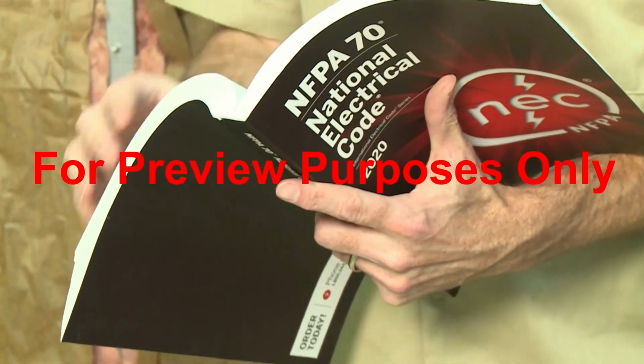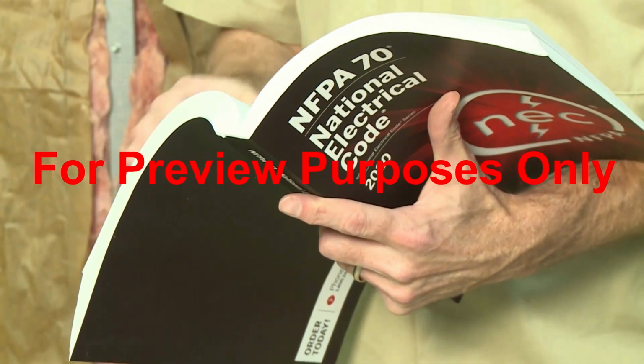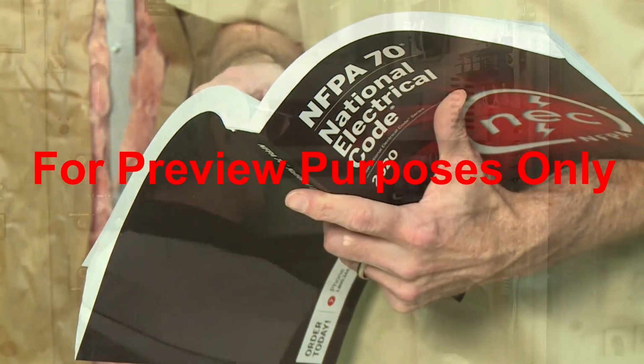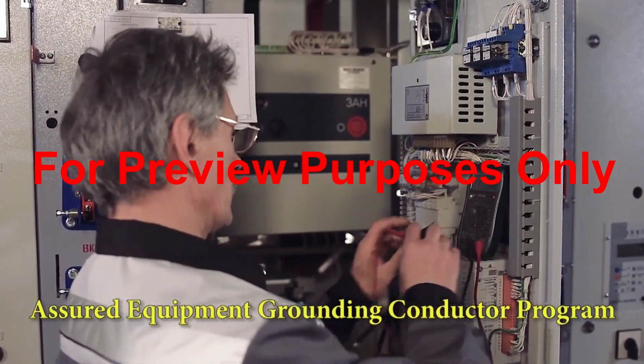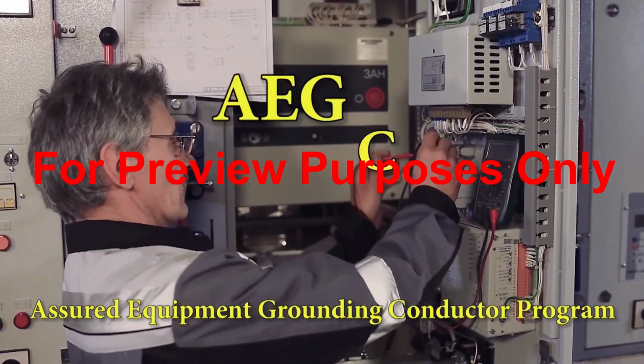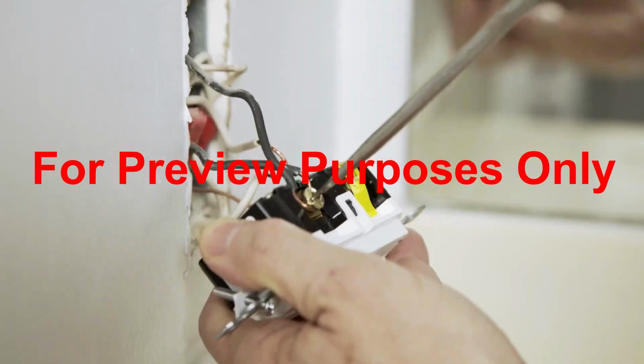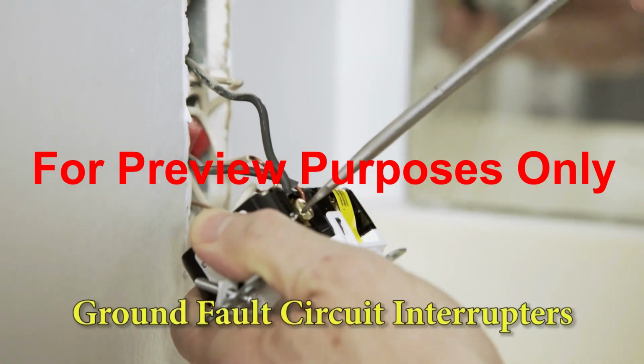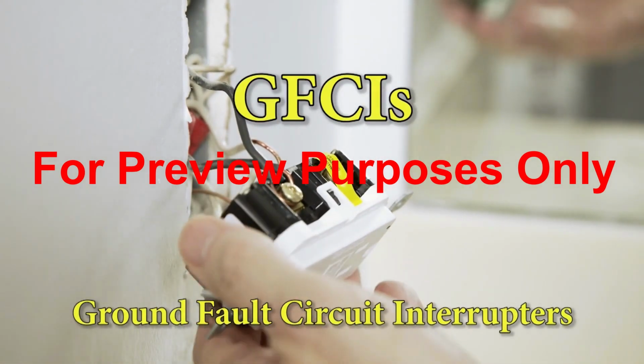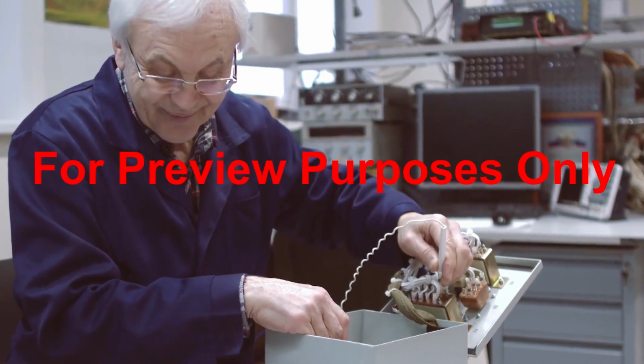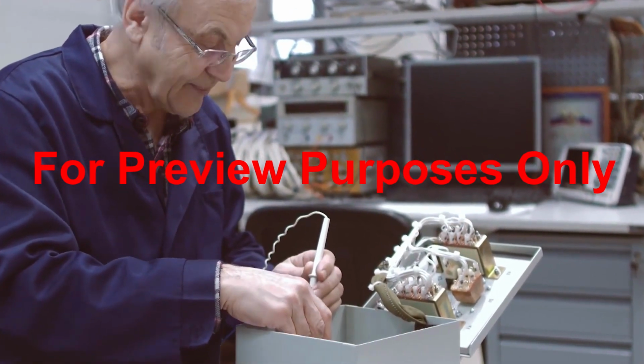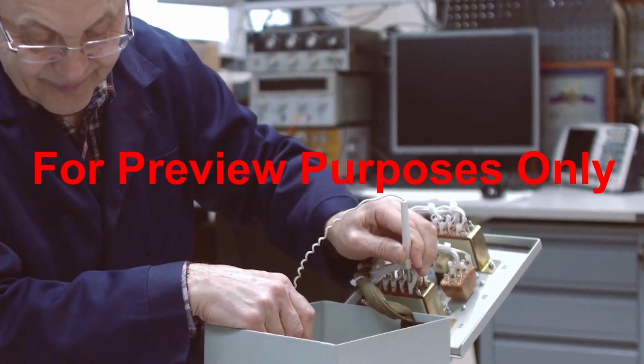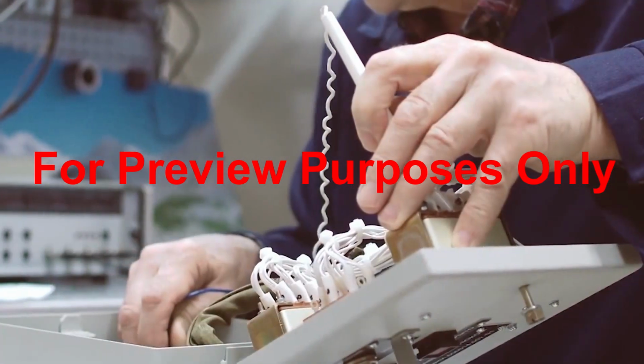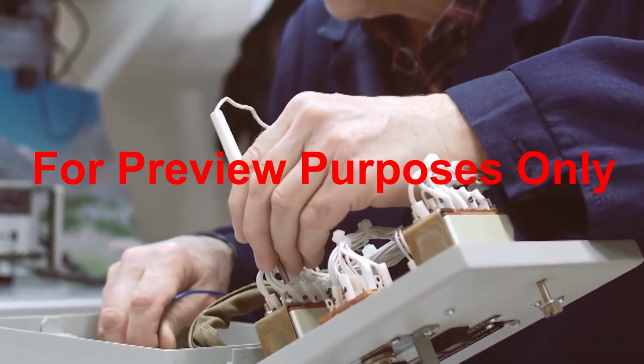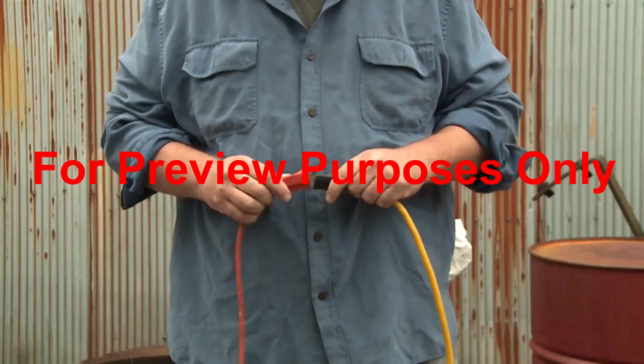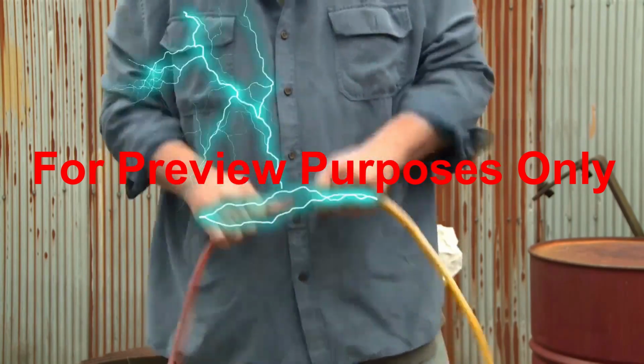OSHA's electrical safety regulations give construction employers two options for protecting their employees from ground faults. One is to create and implement an Assured Equipment Grounding Conductor Program, AEGCP, for each job site. The other is to equip each site with Ground Fault Circuit Interrupters, GFCIs. In an Assured Grounding Program, designated employees inspect and test electrical equipment on the site regularly to ensure that it is grounded. This helps ensure that any electricity that leaks in faulty equipment can find a safe internal path to ground instead of shocking and possibly electrocuting the person using it.